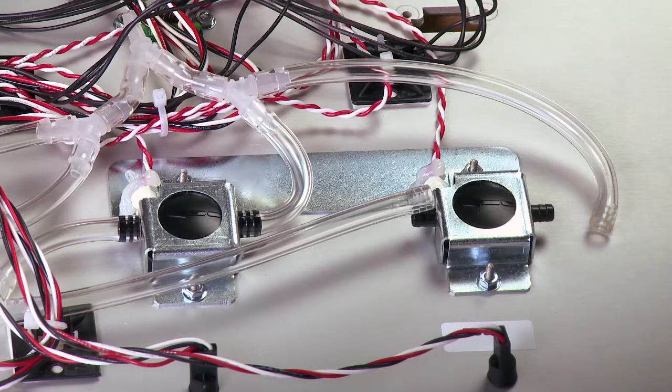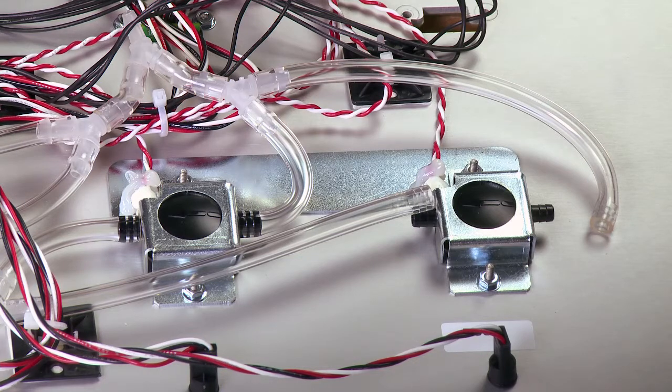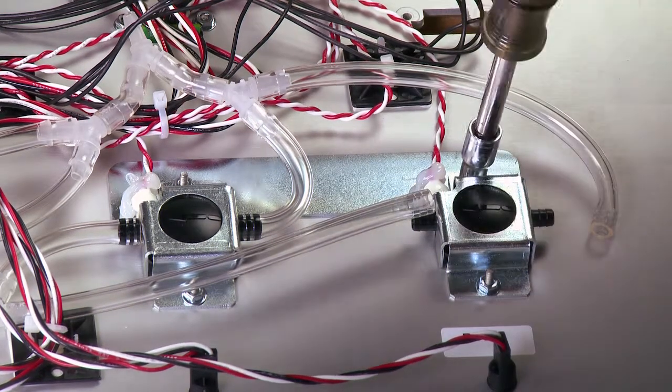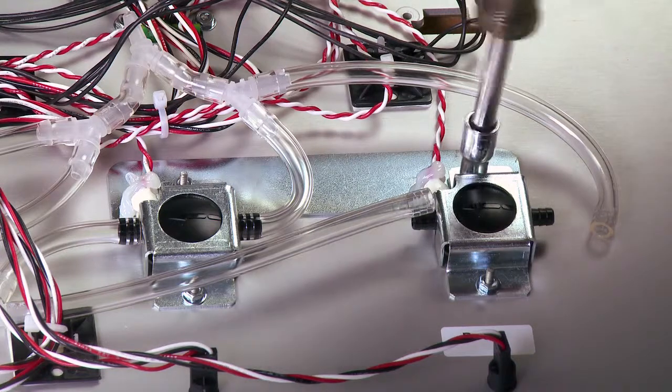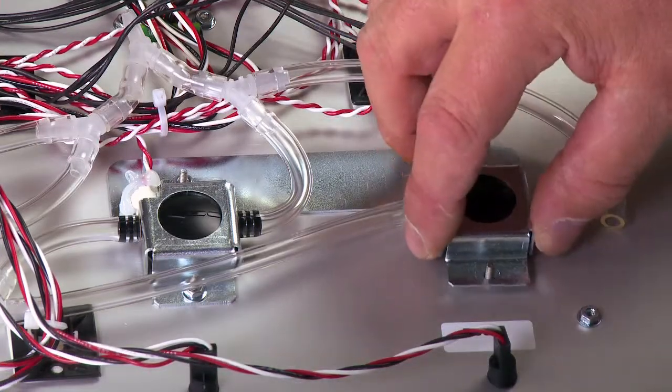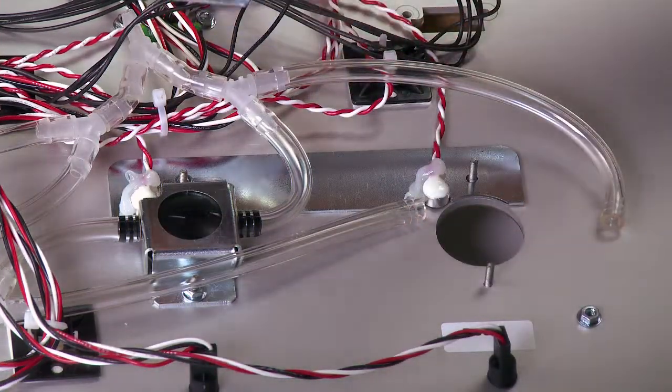Note which tube pertains to which function for reassembly. The next step is to remove the calibration cup holder bracket using a ¼-inch nut driver. Remove the two nuts holding the bracket and lift the bracket straight up to expose the calibration cup.